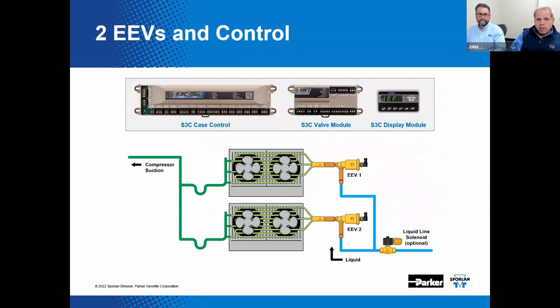Here's another version. Here's the control in 2 EEVs. What's going on here, John? Well, so in that situation, the valve module is basically an extension of the case control, and it expands the control's capabilities. This provides for additional inputs and outputs. Could be control for 2 EEVs or 1 EEV and 1 EEPR.